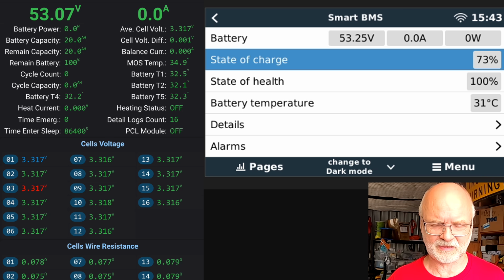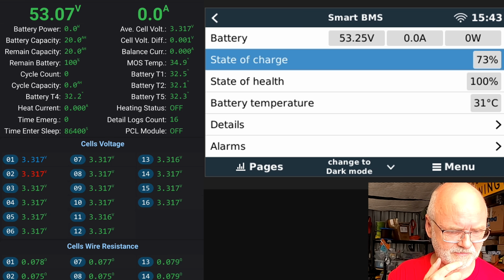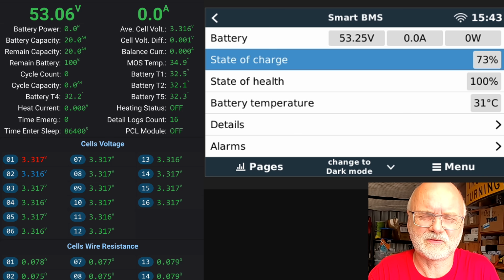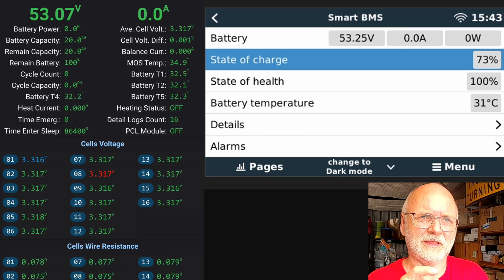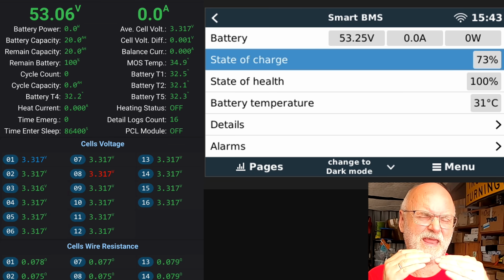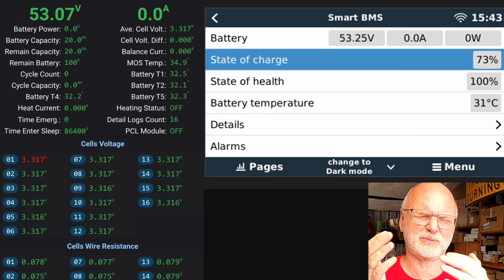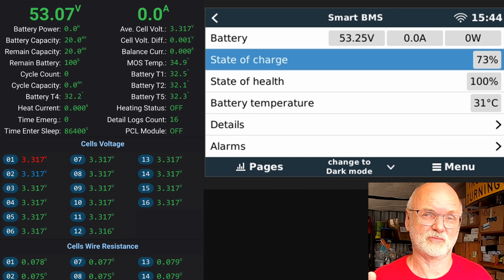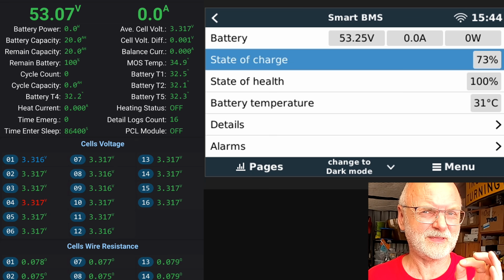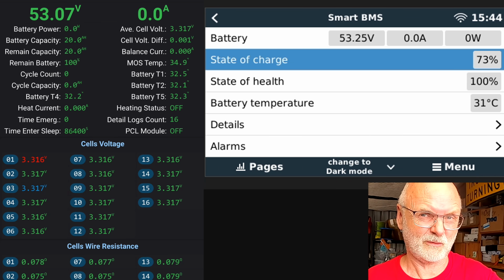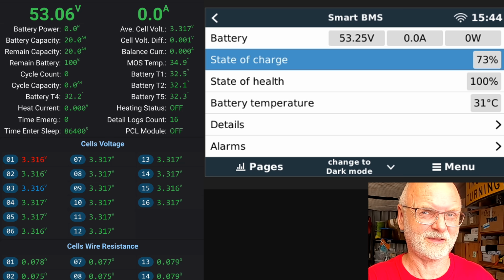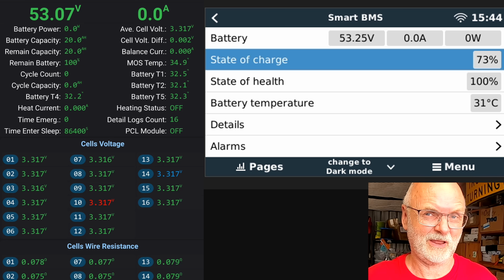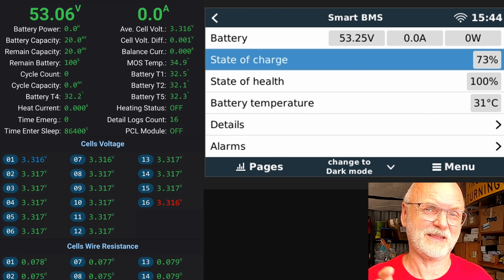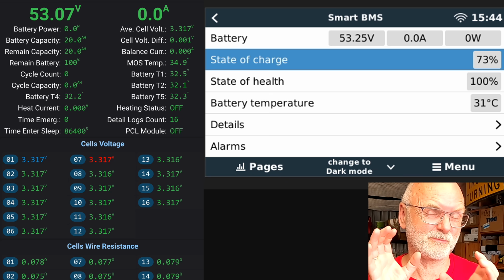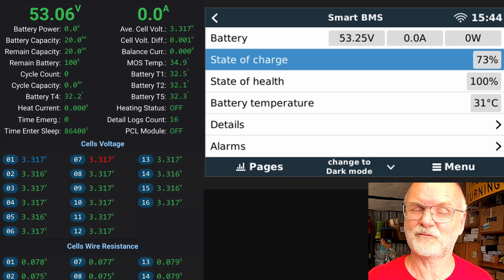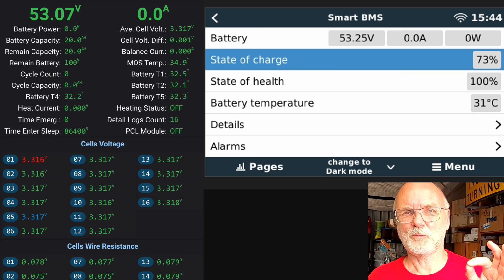Yeah, this one sits on 100%. Okay, that is a bit, what do you think? Is this important? Because usually when you have batteries in parallel, they all have the same state of charge, more or less. There could be 1, 2, 3% difference, but usually they're in the same boat. So is it enough if the master BMS reports its own state of charge to your inverter instead of taking into account all the other state of charges of all the other batteries? Or does it need to read all this data and do an average state of charge and report this to your inverter, which could be slightly different to what the master actually is? How precise do you want to go?